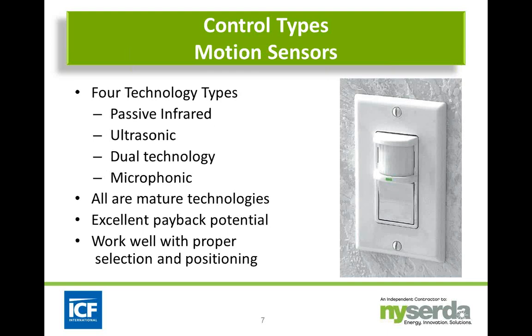There are four basic motion sensor technologies we work with. The first is passive infrared, which reads heat motion within the space. Next is ultrasonic, which sends out a signal into the space. Dual technology is generally a combination of passive infrared and ultrasonic. It could also combine passive infrared with microphonic, which picks up sound within the space and continues to trigger the device, telling the lights to stay on.